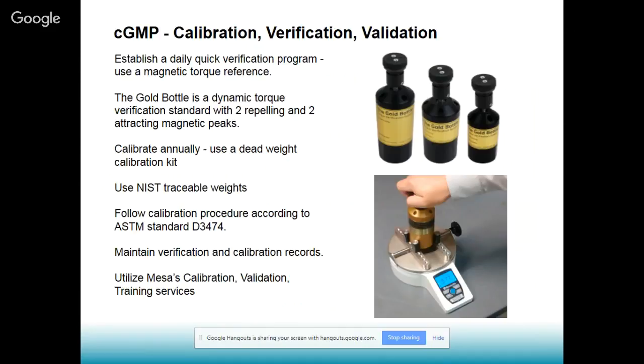Also wanted to give you an idea about the verification, which is different from the calibration, because the verification can be very quick. You just place this magnetic torque reference on the torque tester, and all you do is run it just like if it was another regular product, and it will give a readout on the torque tester display. If the readout is not within the stated torque value on the gold bottle, then you know that the torque tester is going out of tolerance, and you should recalibrate, or you should have it serviced.